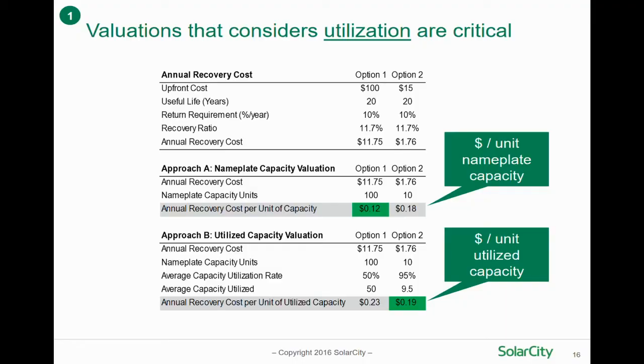If you take this to numbers - I know this is too small to read right now - the way we've typically thought about investments from a financial perspective is you look at the dollar per capacity. So if you're putting in a 20 MVA transformer in a substation, you take the cost of that transformer, divide it by the 20 MVA, and you get dollar per MVA, or dollar per capacity. You go with whatever is cheapest. What it doesn't consider, though, is a lot of that capacity is not used for long periods of time. You can imagine a world where substations are really cheap, transformers are cheap.